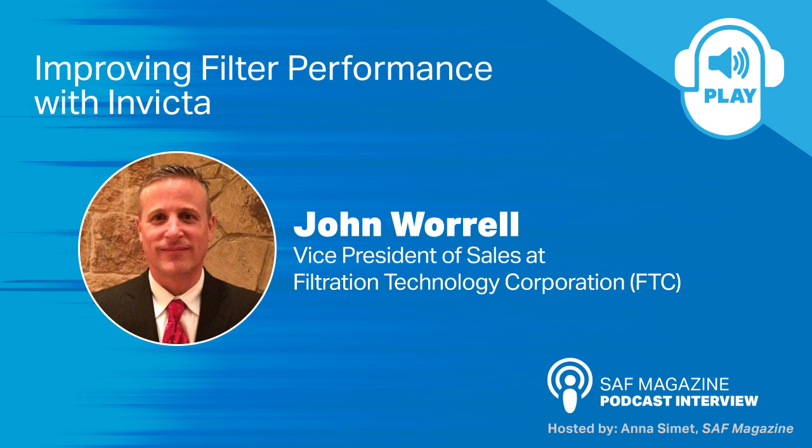Okay, so what about rental vessels? Do you guys have them available? We do. FTC has a full fleet of rental vessels, all ASME code, ranging from 150-pound to 300-pound design. They're all flange connections. We offer them in carbon steel and in 316L stainless steel, from 8-inch diameter up to 36-inch diameter, handling flow rates in excess of 1,200 GPM.